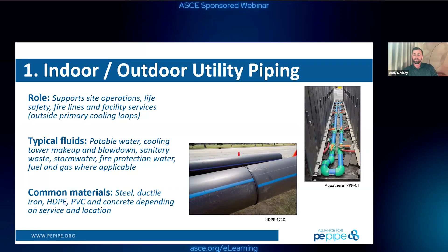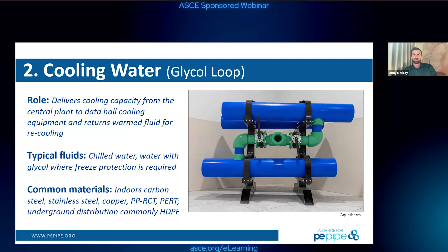So we talked about the underground side—HDPE, the primary player there. As we enter the building, we're seeing really all types of materials: carbon steel, stainless steel, copper, PPRCT, PERT, and some HDPE. These are used in chilled water systems, and it could be a glycol focused system. These piping systems are the backbone of the cooling network.